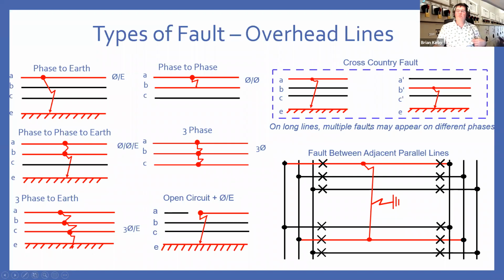Cross-country faults can happen on very long lines. So the UK generally doesn't have a lot of long lines. It's quite a heavily meshed network. But in a cross-country fault, you could have different faults on different phases on different parts of your network. And also, if you have a parallel line, these are common in some parts of the world, not so much in the UK, you could get cross adjacent faults where one phase on one line connects to another phase on another line. So you would see a phase-to-phase fault back on the bus. But again, this isn't common in the UK.